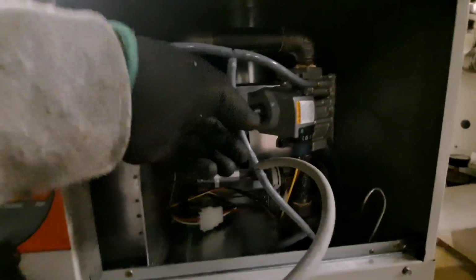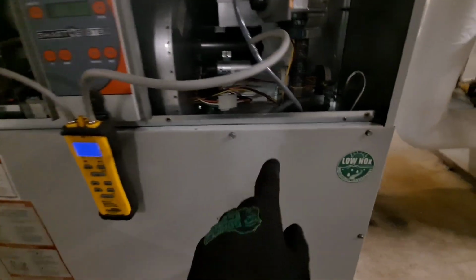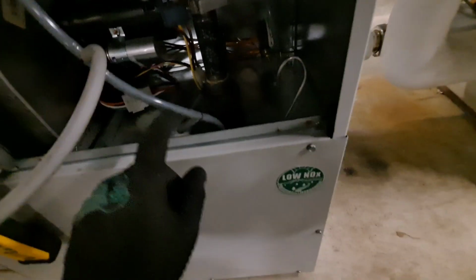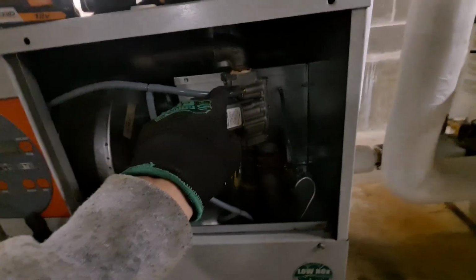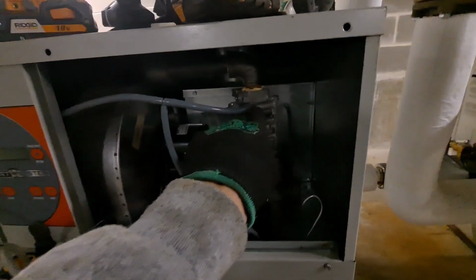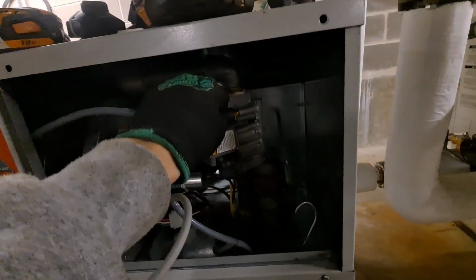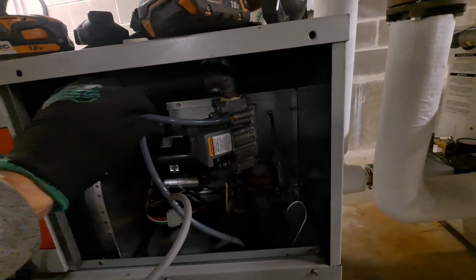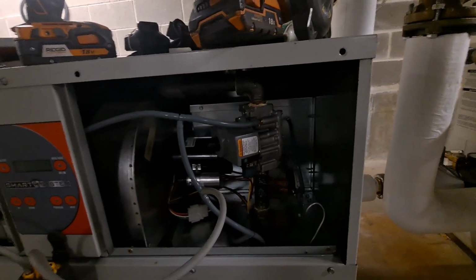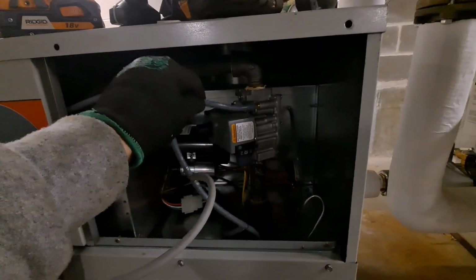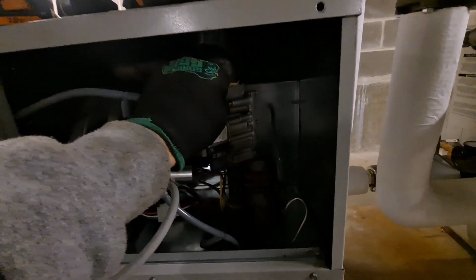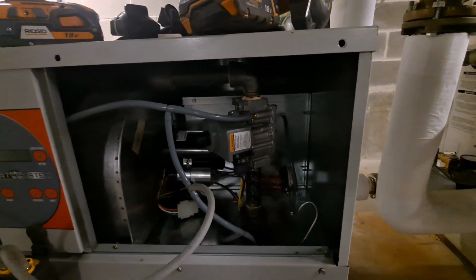So this is a T, and it goes down right here, and this is considered chamber pressure, because remember, this door has to remain on. So that's considered chamber pressure. It comes up and it's using that chamber pressure on these gas valves. That's why you'll see some gas valves have tubing coming off, going to pressure switches and whatnot, and you may be wondering what the hell that's for. Well, it's using it as a reference.